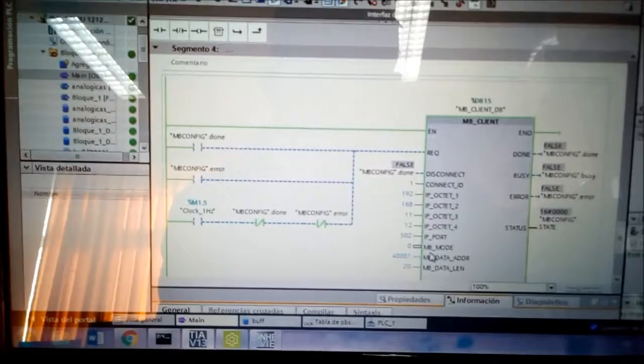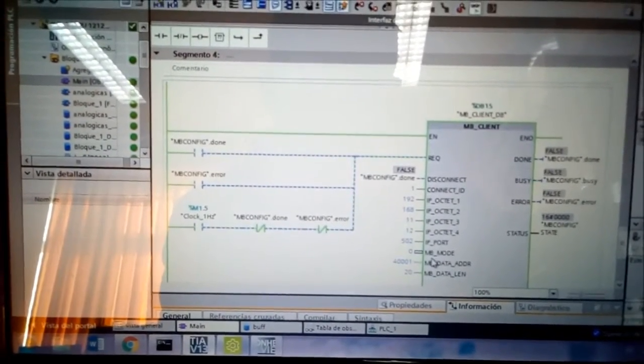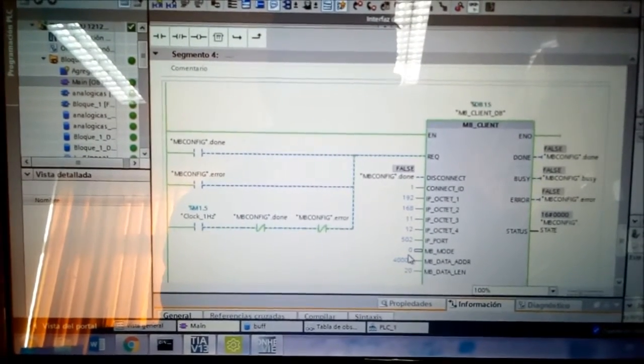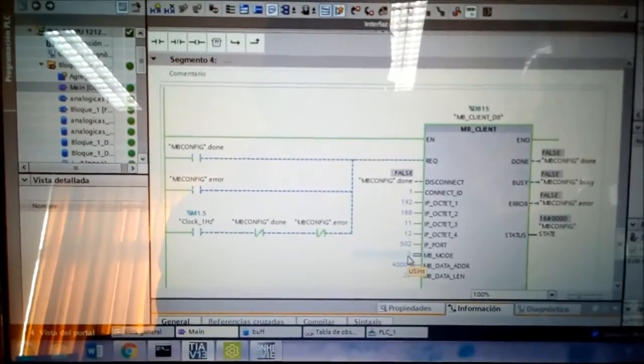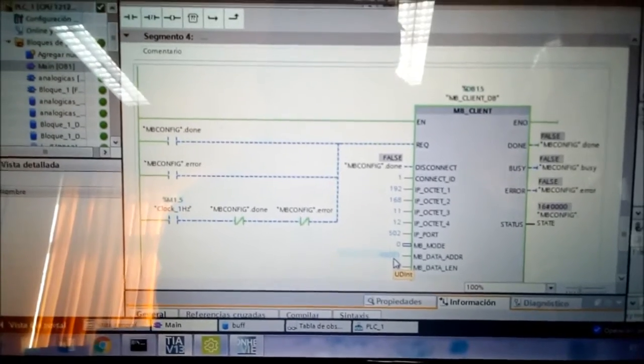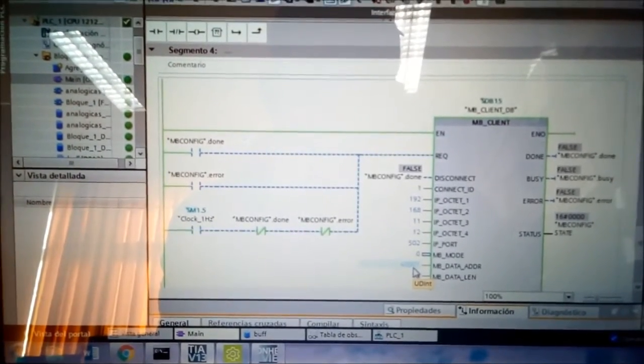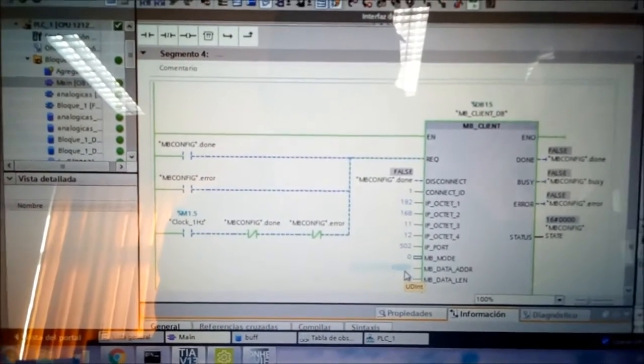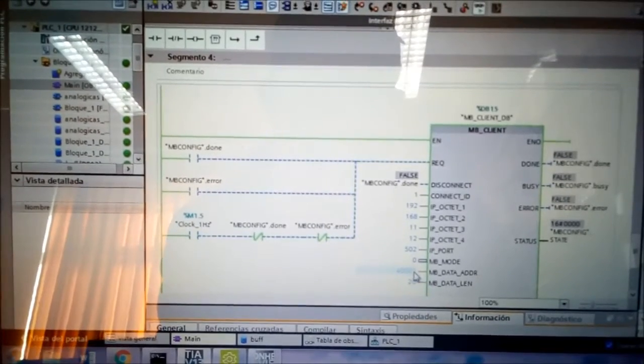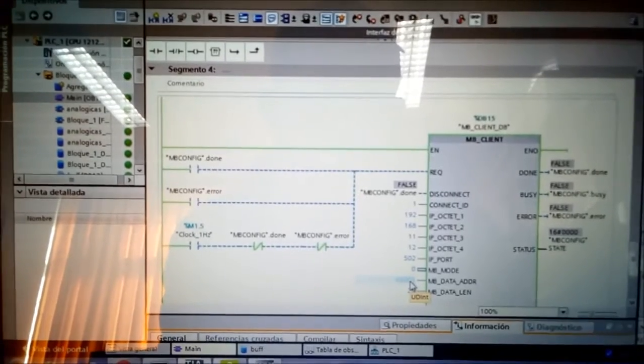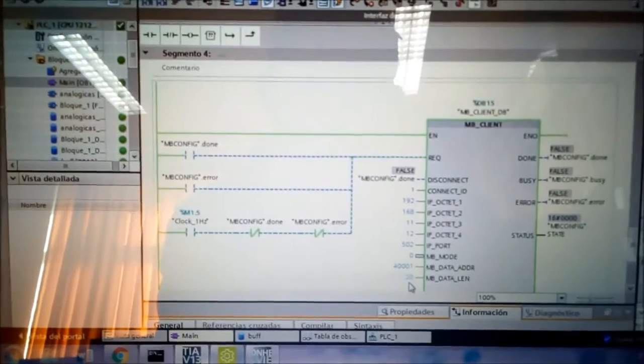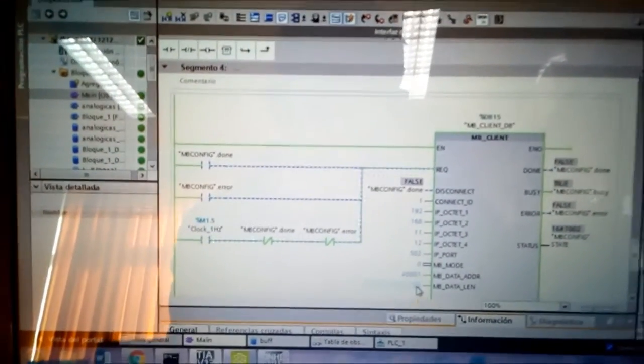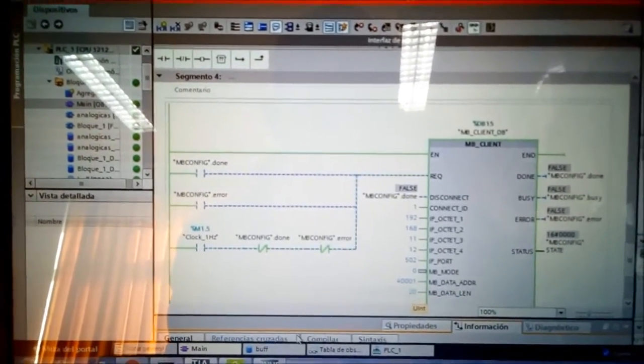The MB_MODE, this number is to tell the block if we are reading, writing, or diagnostics. Right now, zero means we are reading. And this one is the MB_DATA_ADDR from which register of the Schneider PLC we are now reading values. Now, we are reading values from the MW zero register on the Schneider PLC.